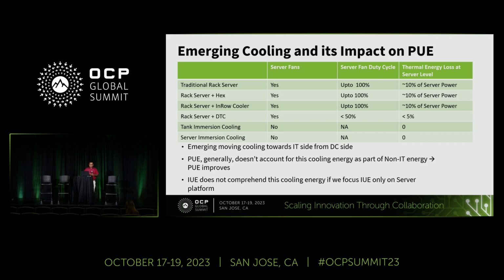If you look at the cooling portion, where the energy is going, yes, there are fans and other cooling materials used. If you look at the power consumed by those areas, it's up to 10% in the traditional sense. But if I'm using immersion cooling, it's not within your system, it is outside your system. So you have to consider rack level rather than system level. Even if you put parametrics, it will vary, but you have to comprehend at a rack level or a tank level to get the whole thing considered for the metrics.